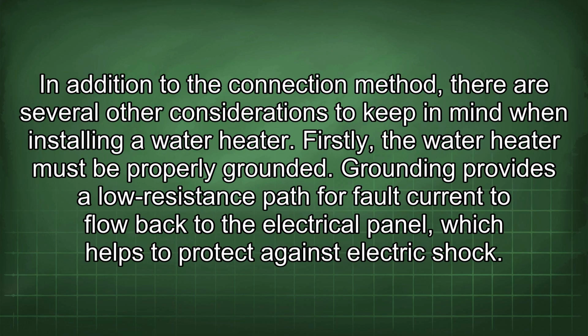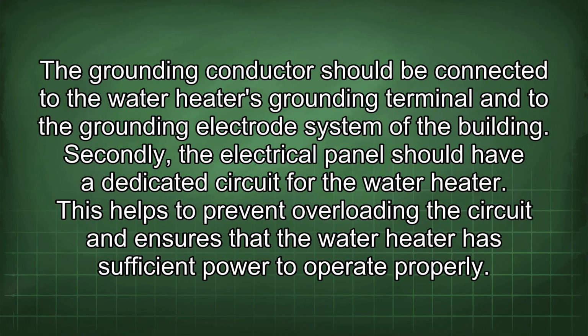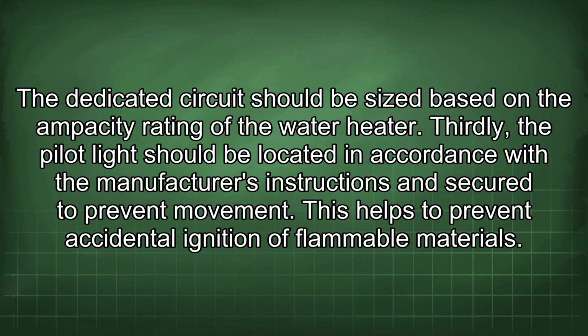In addition to the connection method, there are several other considerations to keep in mind when installing a water heater. Firstly, the water heater must be properly grounded. Grounding provides a low resistance path for fault current to flow back to the electrical panel, which helps to protect against electric shock. The grounding conductor should be connected to the water heater's grounding terminal and to the grounding electrode system of the building. Secondly, the electrical panel should have a dedicated circuit for the water heater. This helps to prevent overloading the circuit and ensures that the water heater has sufficient power to operate properly. The dedicated circuit should be sized based on the ampacity rating of the water heater.